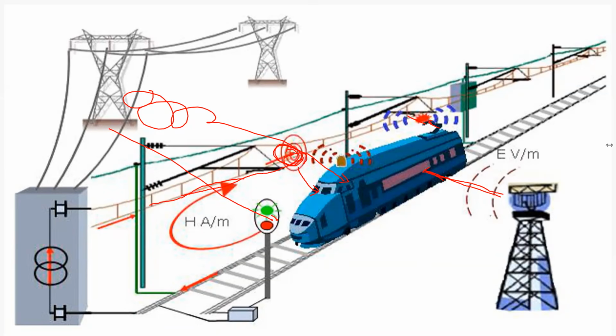Neutral section is not only for EMC purposes. What we are doing with the neutral section is reducing the total length of the AC conductors, so that the magnetic field will not form over a larger extent and spread to nearby premises. That is the purpose - it reduces the magnetic field.